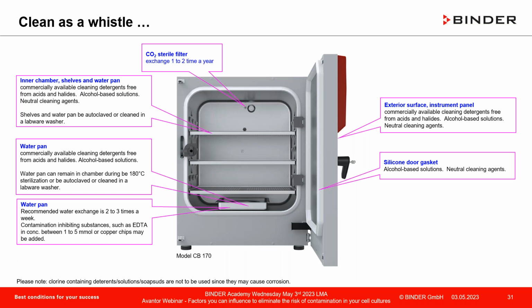Sterile CO2 filter. Now, to get that right, ladies and gentlemen, for many brands, there is a CO2 particle filter, very much like a syringe filter, which all of you probably know. Exchange that 1 to 2 times a year. That is for the incoming gas from the gas bottle. We are there collecting, and all of the other ones collecting for each gas type, CO2, O2, nitrogen, those particles, and that should be exchanged 1 to 2 times a year.